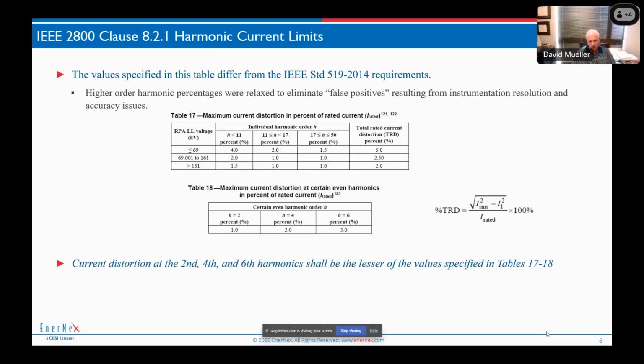We also use an interesting definition where we apply not just harmonic frequencies, but interharmonic or all frequencies. So we take the RMS value and subtract the fundamental and do the orthogonal relationship, and we come up with the TRD definition that way. This was first proposed in 1547, and I think it's a good definition, and it's actually even one that IEEE 519 is considering for its next revision, as opposed to current total harmonic distortion, which depends on how much fundamental you have. So anyway, most plants are going to meet these limits.